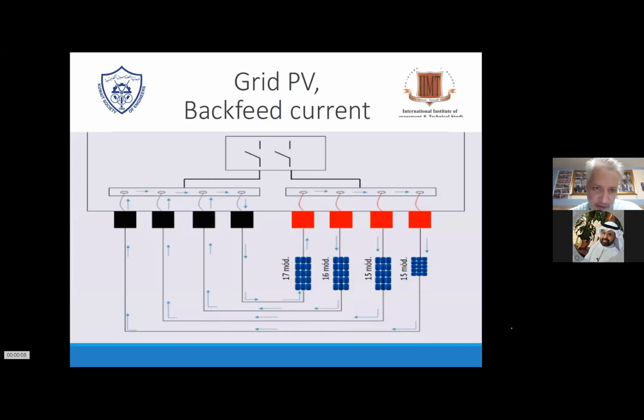So, like I said, in that case there are 17 modules installed, but just to see the flow of the different backfeed, the 17 modules try to backfeed the 16, 15 modules, depending on how much voltage the inverter is generating. So if it, for example, hits the 16 modules, then both of these strings will feed the 15 modules. So if the 15 modules, like I said, are shaded, soiled, or have some other anomalies like lightning strike and diode failures, so they will short-circuit all the time, then those voltages, mostly in the beginning and in the nighttime when they reach 600-700 volt, then these two strings will get the backfeed current. So that's also all these mismatch losses.